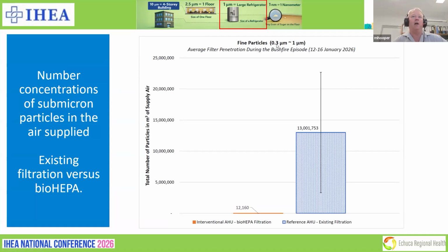Now if we look at fine particles, 0.3 to 1 micron, the average filter penetration during the bushfire period that got through our normal control system with F9s was 13 million particles per cubic metre, up to 22 million. On an average day we have 1 to 2 million particles and we filter 80% of them, but on this day 13 million particles per cubic metre were getting through into our wards, compared to our intervention unit, where only 12,000 particles were getting through. That's not million, that's 12,000.